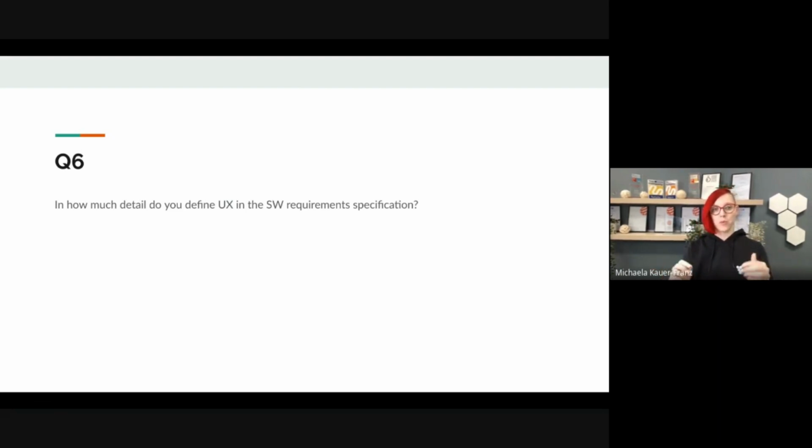So if we write our documents, you will not find one single document that says user interface specification, but you will have a link which then links to the software specification. And there you will have a link which says this is UI related. And the same accounts for all the user interface characteristics related to safety. It will be integrated in the risk management file and cross-linked there. So we try not to make it big, but to integrate it in all the things that you already have.